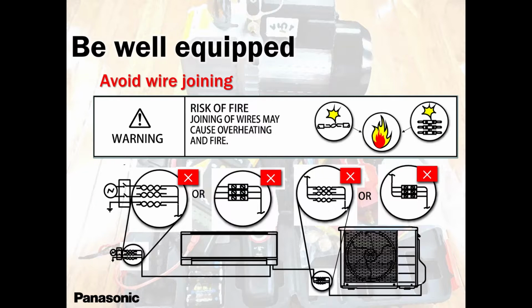And then I said, who did the wiring? And he says, our electrician. I said, can you ask him? And when he asked the electrician, yes, the electrician did join in the basement before he went to the indoor unit or before going to the outdoor unit. And that's where the problem is. So please keep in mind, we don't want any joints. It is causing an H11 error code. It's a nuisance error code once in a while.